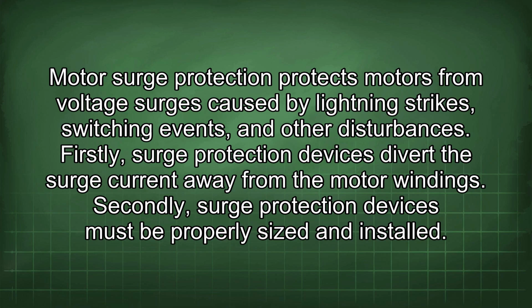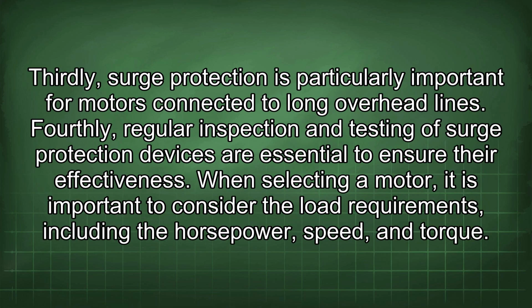Motor surge protection protects motors from voltage surges caused by lightning strikes, switching events, and other disturbances. Firstly, surge protection devices divert the surge current away from the motor windings. Secondly, surge protection devices must be properly sized and installed. Thirdly, surge protection is particularly important for motors connected to long overhead lines. Fourthly, regular inspection and testing of surge protection devices are essential to ensure their effectiveness.